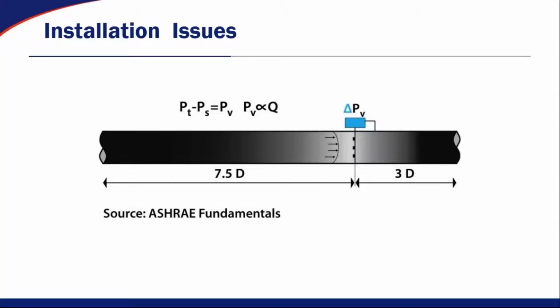Now, we all know in buildings that's pretty rare to get that much straight duct. Typically, you might get 1.5 to 3 duct diameters on either side of that flow measurement device, and that's obviously going to reduce the accuracy of that particular device.